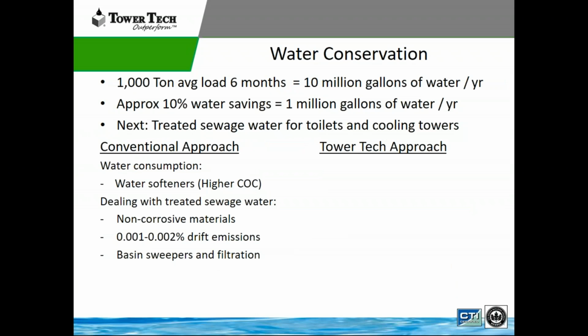From a water side of it, we're talking about a typical 1,000-ton chiller plant, with an average load of 6 months. It uses about 10 million gallons of water per year. So the TowerTech will save approximately 10% water, which is 1 million gallons of water per year. What's going to happen next, and is starting to get adopted in California, is using the treated sewer water effluent for toilets and cooling towers. The problem with that is the treated sewage water is rich in potassium, and on a conventional tower system, which is galvanized and sometimes has a stainless steel basin, it could eat the material. And on a traditional conventional cooling tower, that motor is also in the airstream. So that water is hitting your gears and your motors before it dissipates, versus a TowerTech tower, where the fans are on the bottom, so that water is not affecting the fan system on that cooling tower.